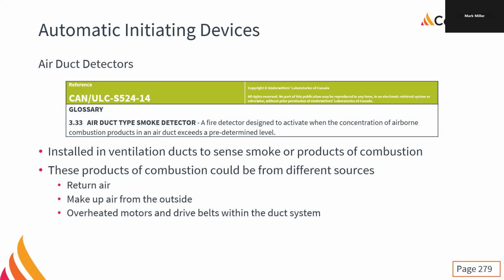Usually it's on the return air, right? We're picking up smoke from somewhere else and sending it back through the air handling unit and inside. Unless, of course, there's a giant fire next door and we're running 100% fresh air, then we totally could be sucking it in from outside.